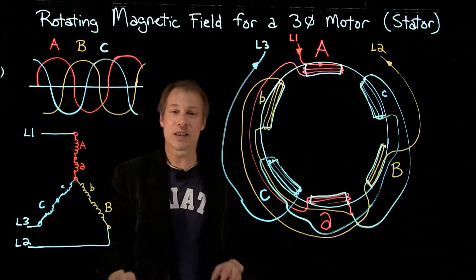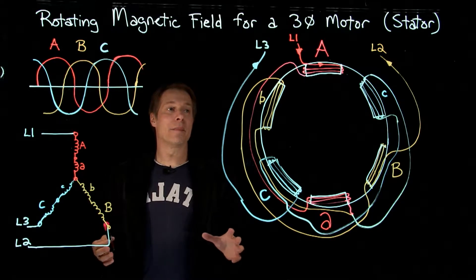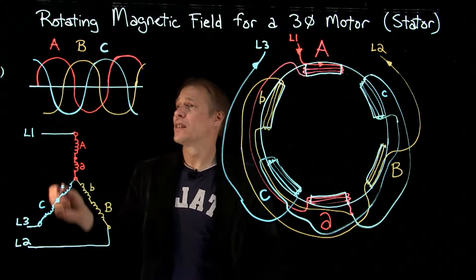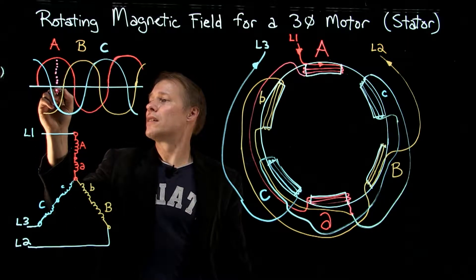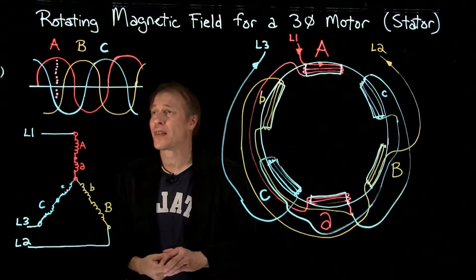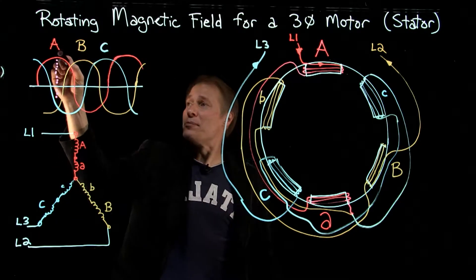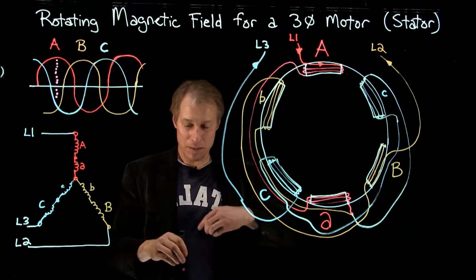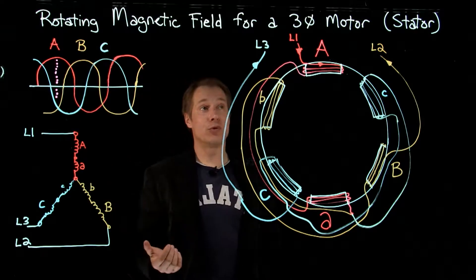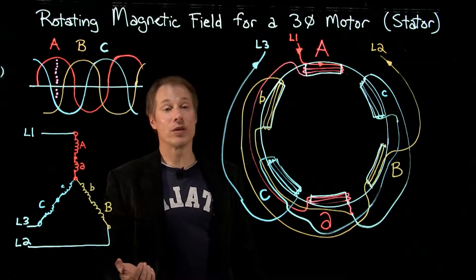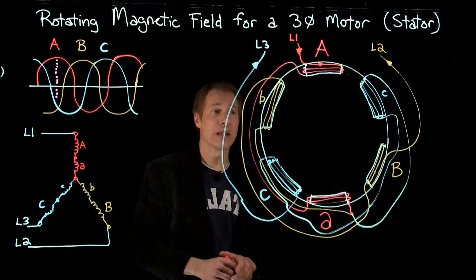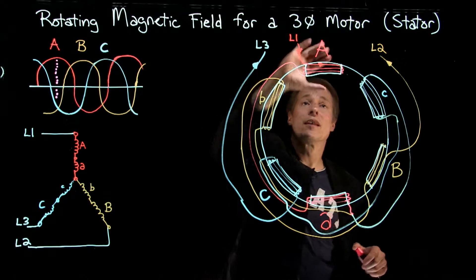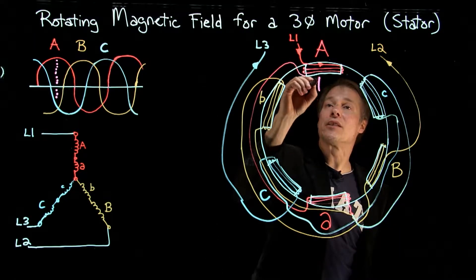What we're going to do is look at a snapshot in time and see what the magnetic pole orientation is. I'm going to choose this point right here where the A phase is at its maximum current, which will give us the maximum magnetic pole. I'm going to use my left-hand rule for coils — that was covered in a previous video. Fingers in current direction, and that gives us the north pole here.